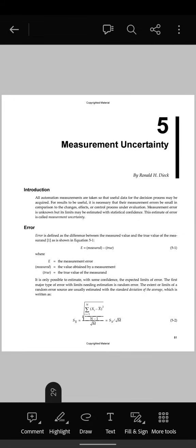Measurement uncertainty. Introduction. Automation measurements are taken so that useful data for the decision process may be obtained. For results to be useful, it is necessary that their measurement errors be small in comparison to the change, effects, or control process. Under evaluation, measurement error is unknown, but its limit may be estimated with statistical confidence. This estimate of error is called measurement uncertainty.